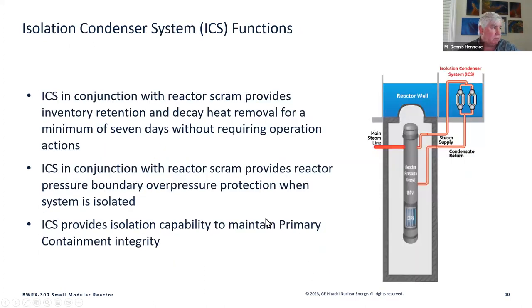And again, I think I missed it on one of the previous slides, that this isolation condenser not only provides the safety function for heat removal, it is also our primary pressure control. With the longer vessel, very large steam space, when the isolation condenser opens, those need to control the design pressure of the vessel. There is a non-safety related pressure relief system that's there as a defense in depth measure. The pressure control is from the isolation condenser system.